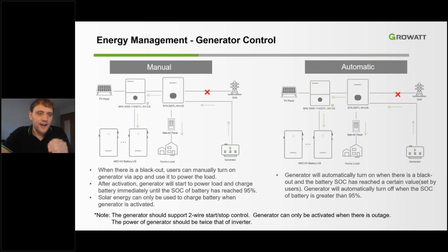Again, batteries are not entirely needed for this operation. In this case, sizing the generator appropriately will be absolutely necessary, as the excess generator energy will not be going towards the battery, instead the customer's load panel.